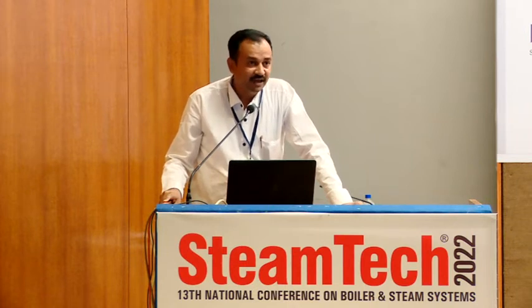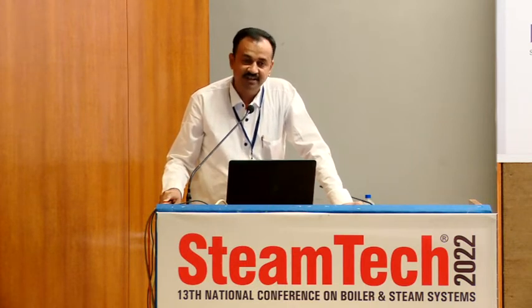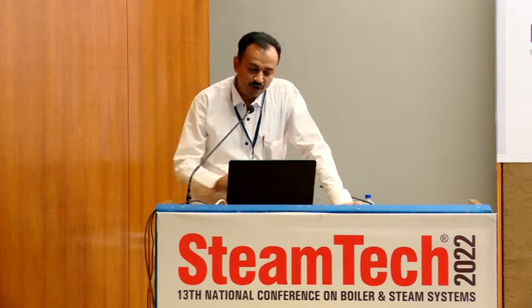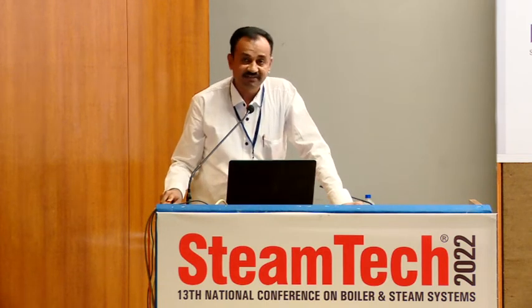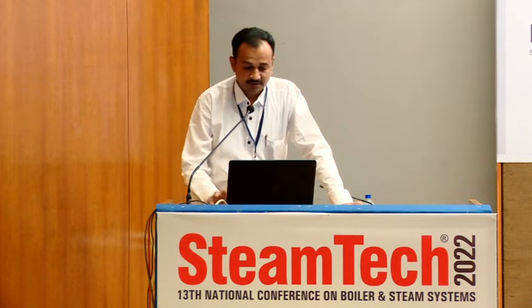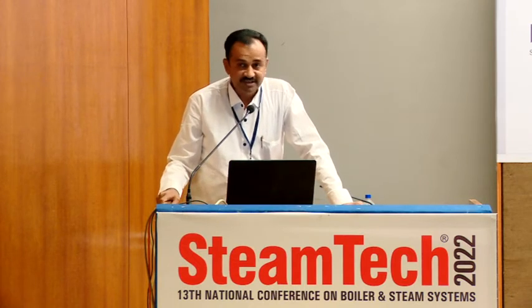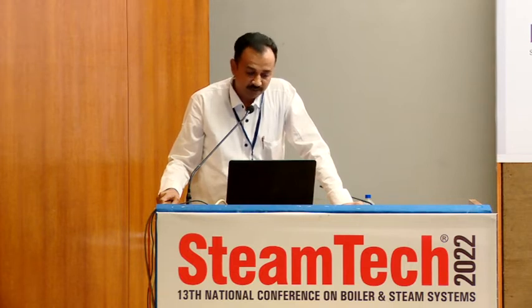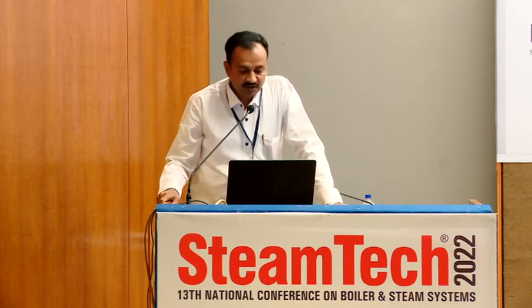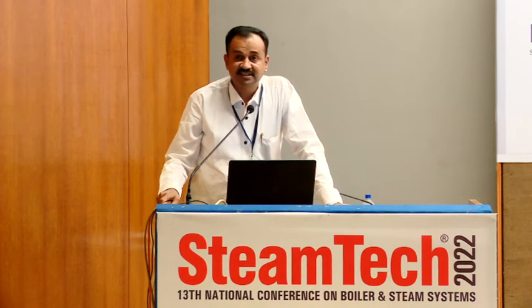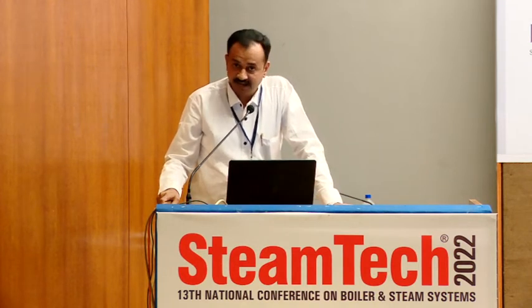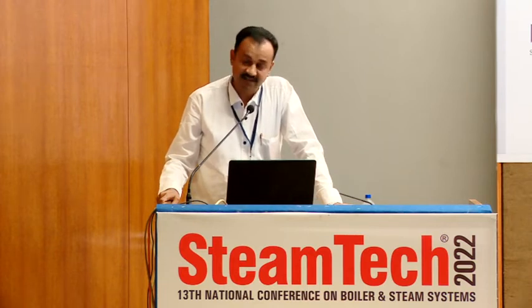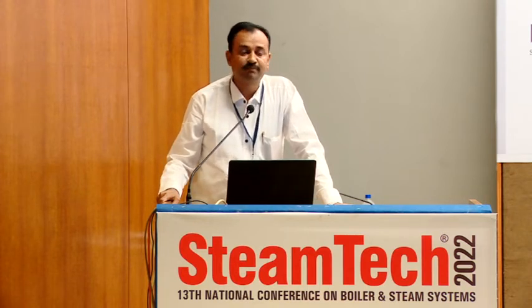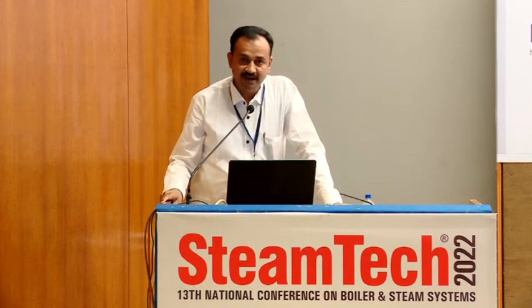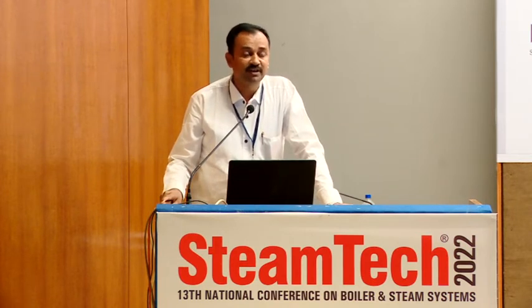So how can the user improve the steam to fuel ratio, SFC, so that he can narrow down this loss and have better efficiency available for that boiler house? What we suggest to the user is that connecting the boiler house on cloud will help in sustaining the boiler house: first uptime, then efficiency, and then safety. Sure, safety is the utmost priority, it cannot be left out, but all these three put together will suffice the requirement and will give the better advantage.